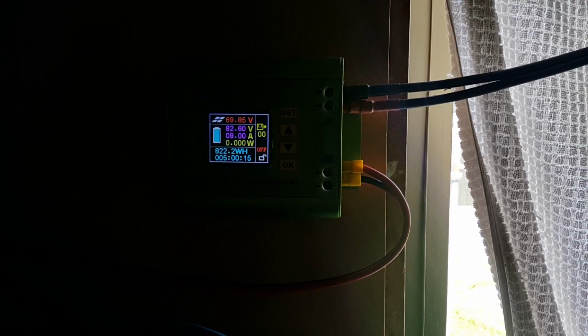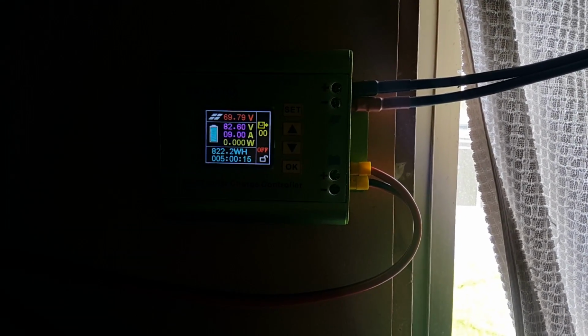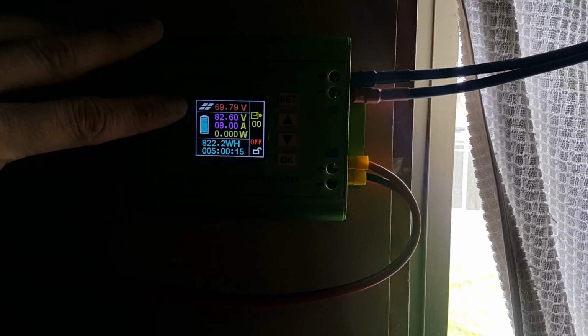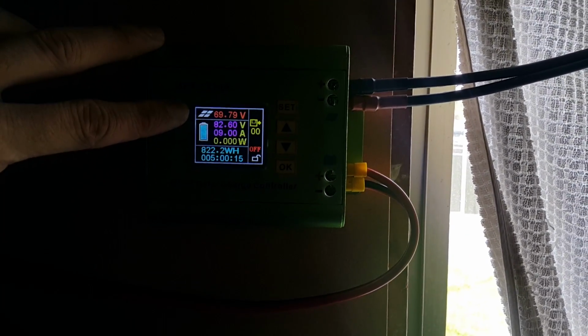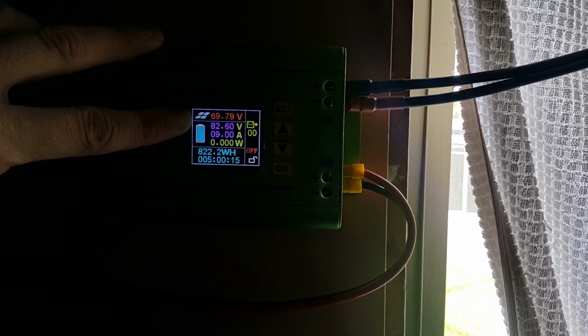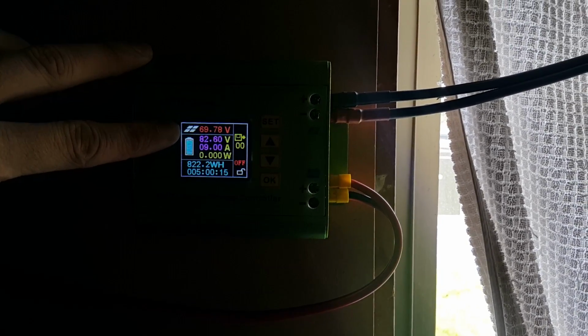So this is a good idea about how it's running. The solar panels have got pretty much full sun, or almost full sun anyway. The angle's not perfect, but it's pretty good. But as you see, we're over voltage at 69.8 volts. I've seen that get as high as 78 or 79 volts, so it's way too high for it.